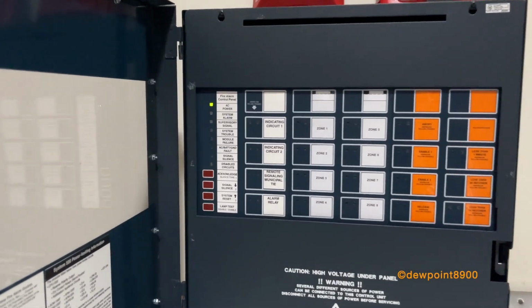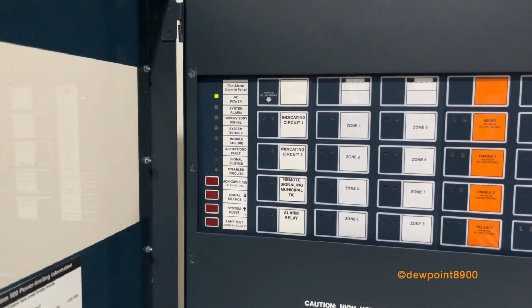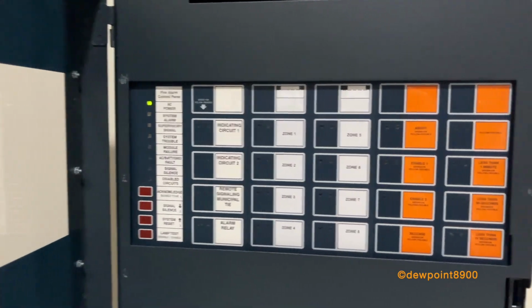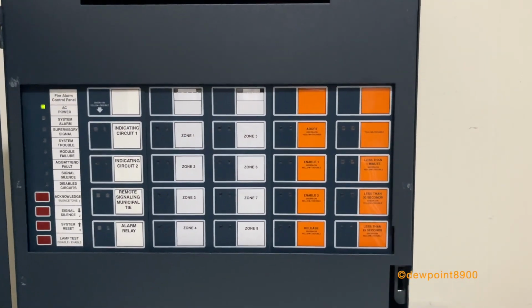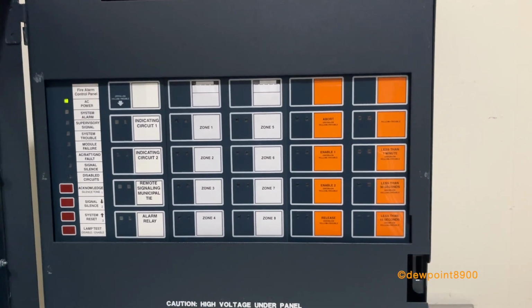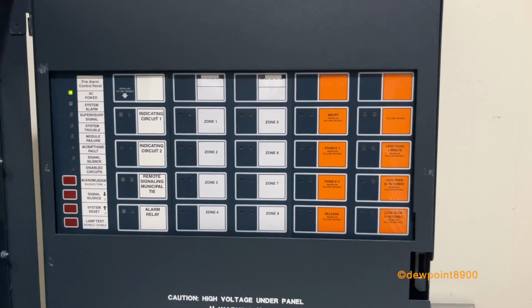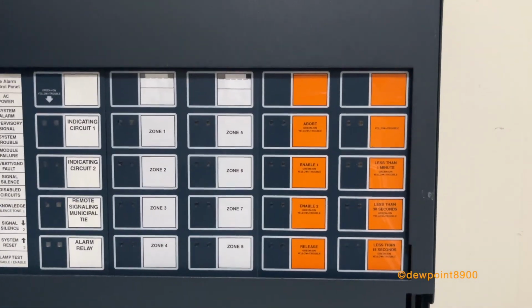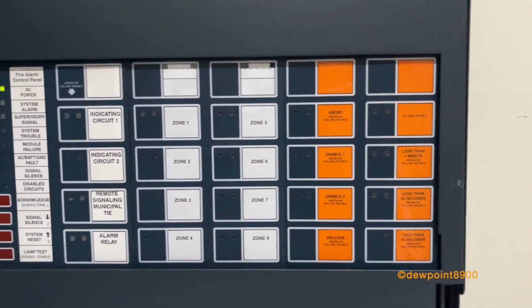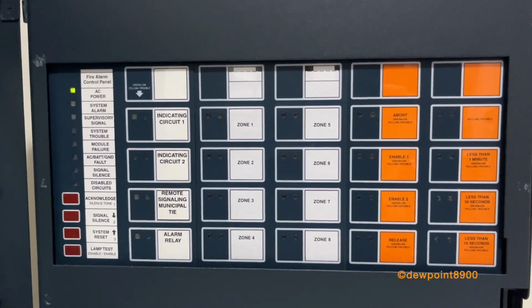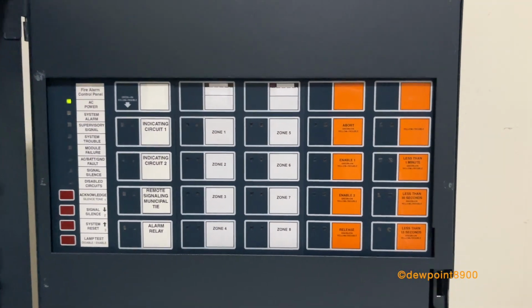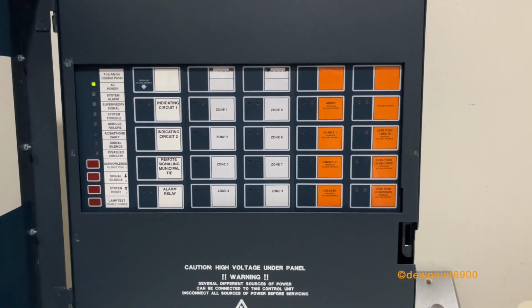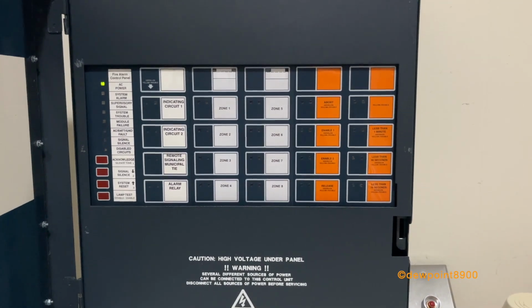The CPUs are also slightly different. The System 500 can only have up to 2 rows of modules, these in the front and some right behind the same cards, whereas the System 5000 CPU can have up to 4 rows of modules. System 500 cards also lack any buttons below the LED indicators, which can be used to turn on outputs or indicate mapping on the inputs. But oddly enough, you can use System 5000 cards on a System 500 and vice versa.